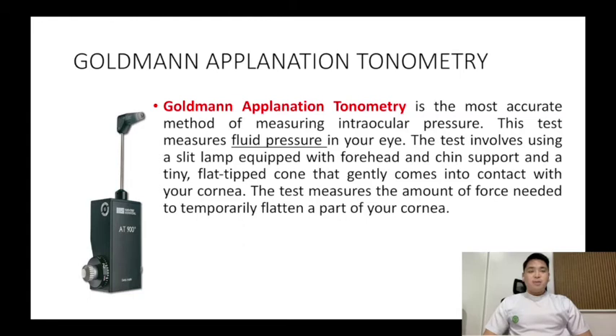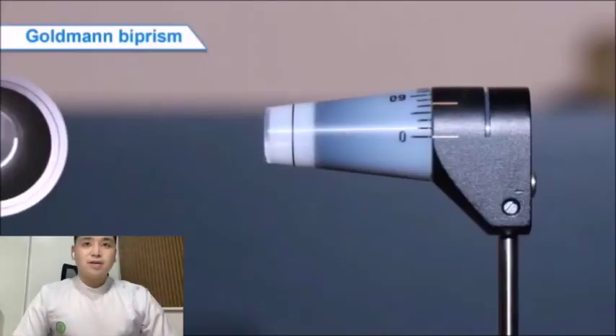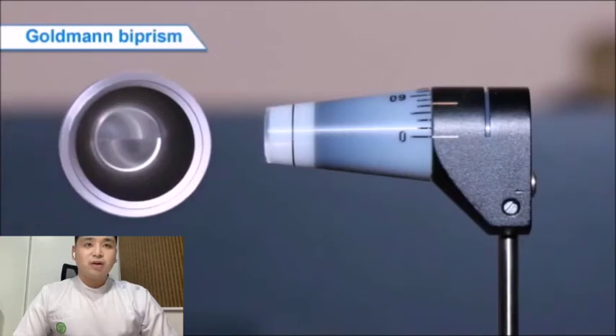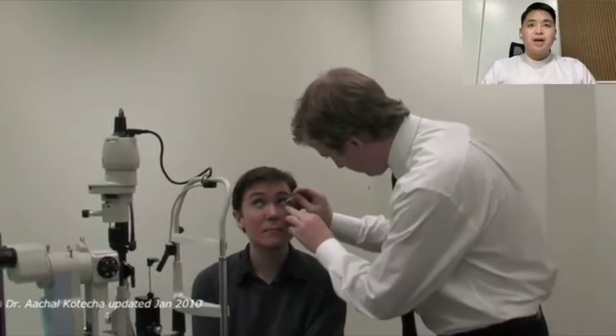Goldmann applanation tonometry is the most accurate method of measuring intraocular pressure. This test measures fluid pressure in your eye. The test involves using a slit lamp equipped with forehead and chin support and a tiny flat-tipped cone that gently comes into contact with your cornea. The test measures the amount of force needed to temporarily flatten a part of your cornea. Insert the clean tonometer tip in the biprism holder. The 180-degree marking on the tonometer tip should be aligned with the white line on the biprism holder. Instill a topical anesthetic drop and fluorescein dye into each of the patient's eyes.